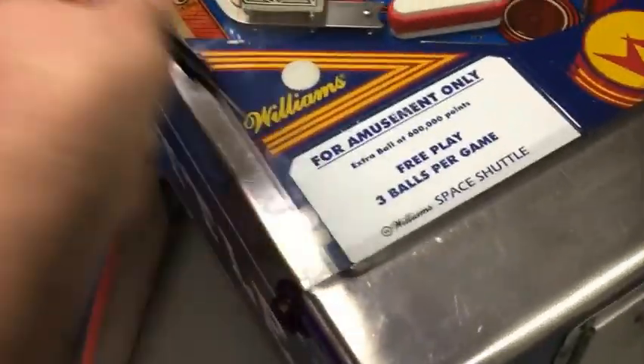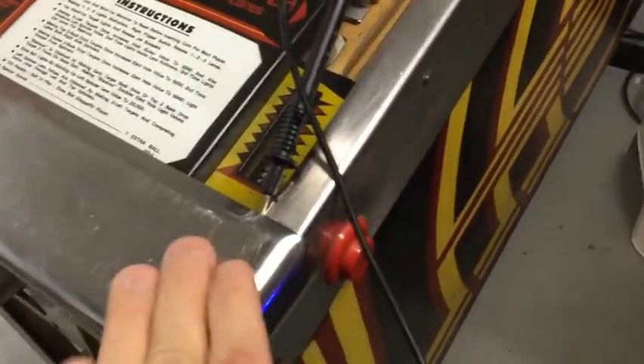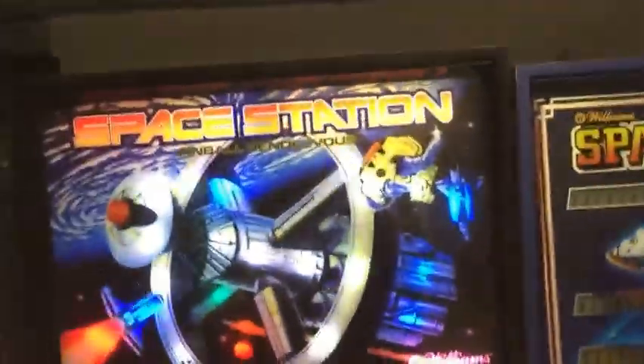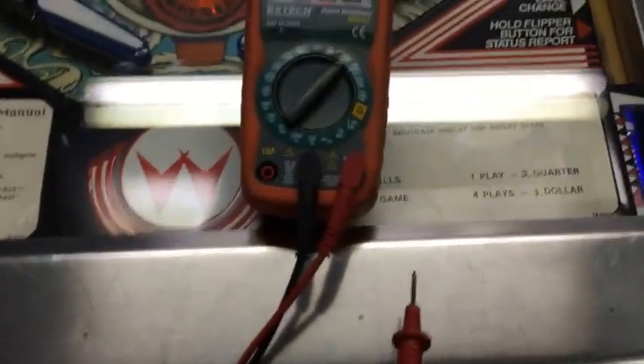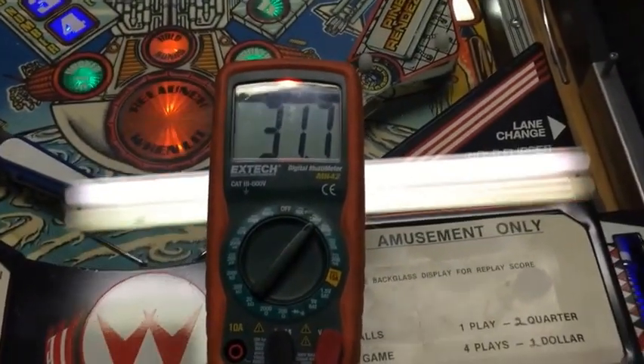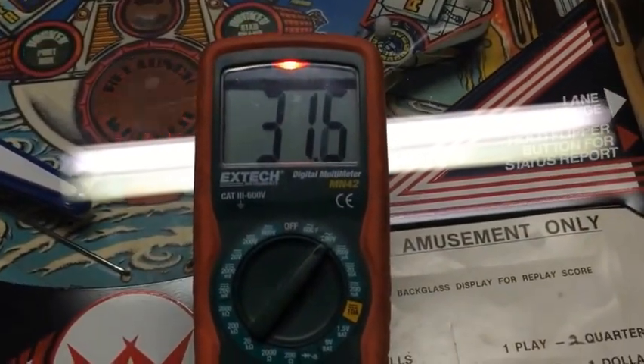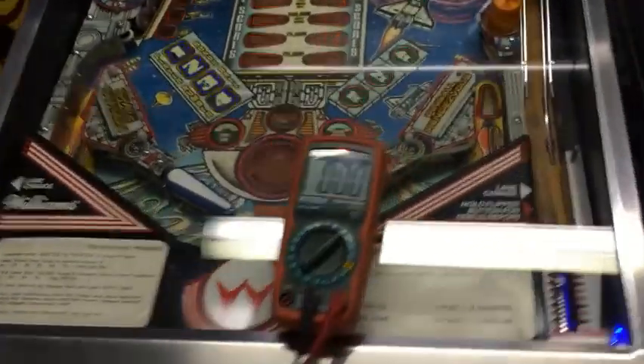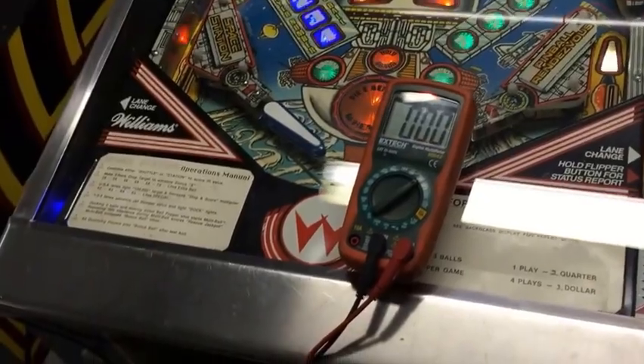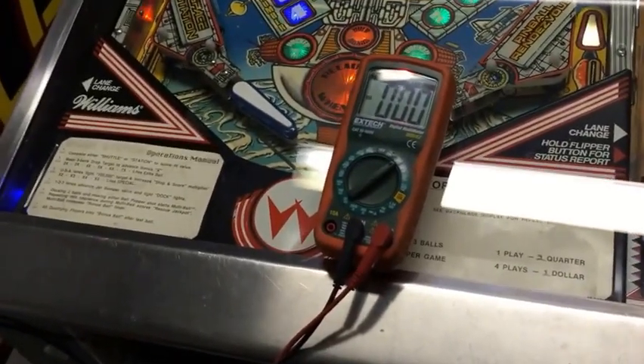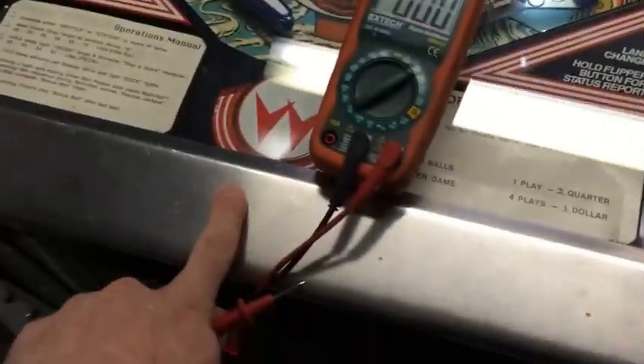Now I'll take my ground and move it over — well, it's not really a ground when testing AC — and put it on this metal on Firepower. Now I go back to the Space Station, which is my suspect machine, and touch it. I'm also getting the 32 volts here. So what that tells me is that somewhere, 32 volts AC is leaking onto the ground.